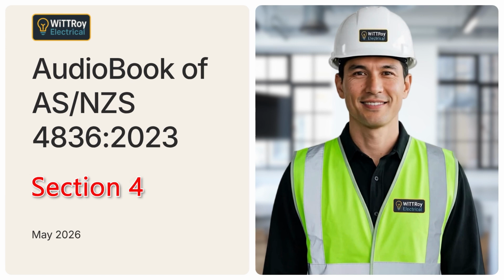Isolation must always be considered first. This may mean rescheduling the work to a time when the equipment can be de-energized. If isolation or barriers cannot be used, a safety observer may be required as another control. Only a competent person may carry out the work. Precautions must be used to prevent simultaneous contact with conductors at different voltages. Precautions must also prevent contact between a live conductor and earth.